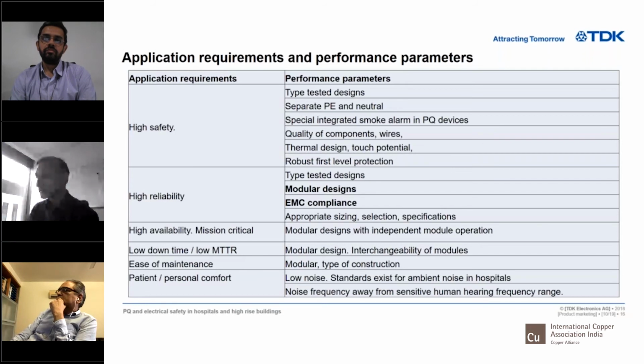Another one is a very high level of availability. That means you need to go for modular designs. I'll maybe show you some examples of what these modular designs are. An independent module operation, so that when one module fails, the rest of the equipment still operates and gives you the power, so that you can at least start your emergency shutdown measures. Very low downtime and MTTR, because it's a critical installation. Again, you should have a modular design, interchangeability of modules, etc. Ease of maintenance, again modular in type of construction.